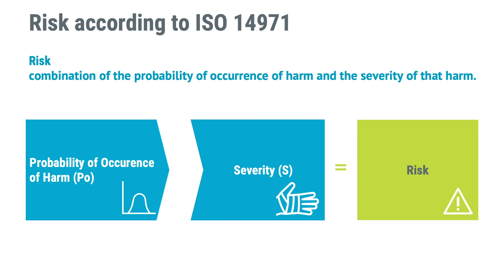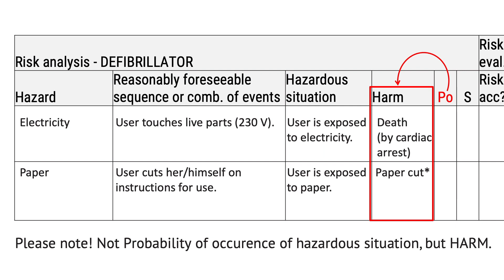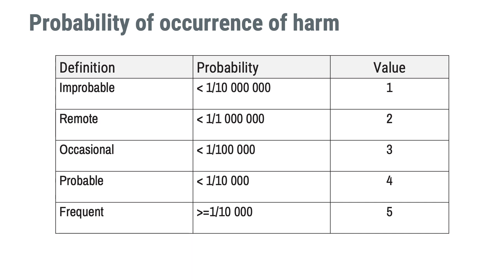Something that is highly unlikely to happen but with severe consequences will get a median risk level, and the same could be said about a risk that is likely to happen but with very low severity. The probability of occurrence of harm is commonly abbreviated as PO, and severity is abbreviated as S. The most common way to assess PO is semi-quantitatively, so that a certain probability of harm arising is related to a number. For example, if the probability is greater than 0.01%, that may be represented by a 5 on a scale from 1 to 5. And if the probability is less than 1 in 100,000 patients, that would mean PO is 3 on the same scale.